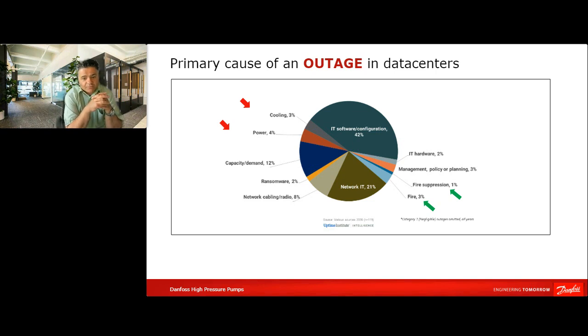And also, you can see on the bottom right that they have highlighted two issues. One is the fire, and the other one is fire suppression. So what does that mean? The fire, which according to their survey is about 3%, means that a fire has occurred and the existing fire suppression system, whatever it was, has extinguished the fire, and there has been damage, there has been outage, and this has been registered. That's one thing. But the fire suppression, which is 1%, means that there was a fire and there was a fire suppression system there, but it was not properly working. The fire suppression might have failed and was not reliable enough.